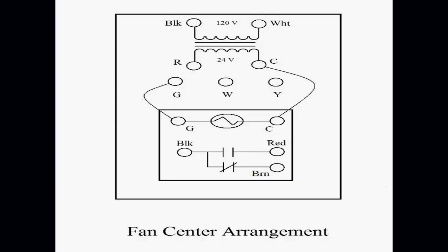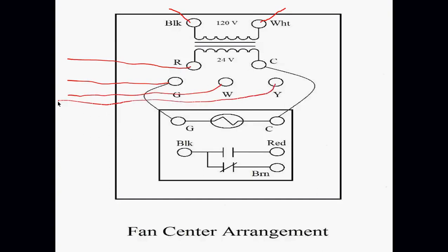This is probably one of the most important diagrams of fan centers that I can give you. Again, this is a pictorial. This is not a ladder diagram. This is a pictorial. It shows you how to wire. We take our line voltage in there. We take our neutral into white. We take our thermostat G to there. We take our thermostat R to there. W to the thermostat, Y to the thermostat. Y also connects to my outdoor unit. C connects to my outdoor unit. Okay? That's how easy this is.